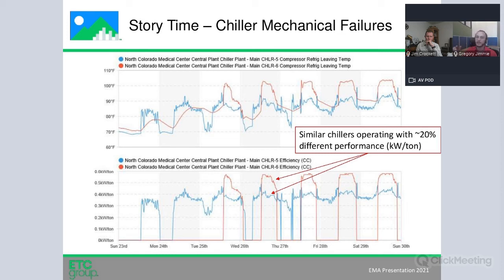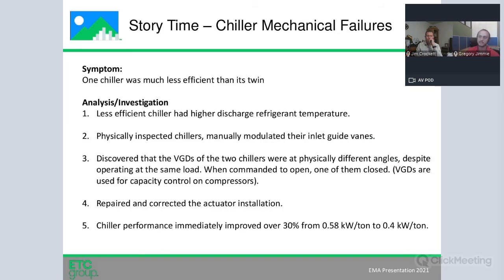We physically were looking at the way the actuators on those variable geometry diffusers were moving the dampers, if that is a good way to think about it. One of them on chiller 6 was about 90 degrees different from the one on chiller 5 when they were at the same position. We were like, that's got to be it. That's part of the problem. So what we did is we got approval from the facility to shut down this chiller, let us make the repair, reorient the actuator on that shaft, and then fire the chiller back up.